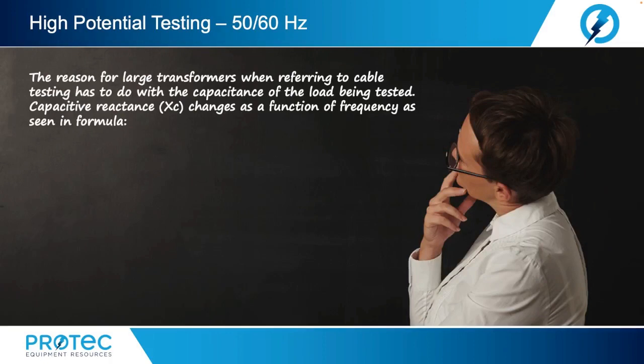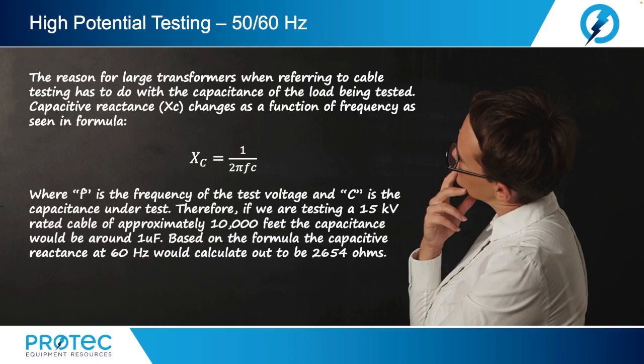Now, the reason for the large transformers when referring to cable testing has to do with the capacitance of the load being tested. Capacitive reactance, or X sub C, changes as a function of frequency, as seen in the formula: capacitive reactance equals 1 divided by 2 pi F C, where F is the frequency of the test voltage and C is the capacitance under test, or the capacitance of the cable. Therefore, if we're testing a 15 kV rated cable of approximately 10,000 feet in length, the capacitance would be around 1 microfarad. Based on the formula, the capacitive reactance at 60 Hz will calculate out to be 2,654 ohms, as we see here.